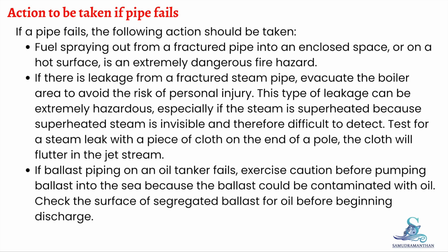In the event of a fractured steam pipe, personnel must evacuate the boiler or machinery space immediately. Steam leakage can cause severe personal injury, especially when the steam is superheated. Superheated steam is invisible and therefore extremely dangerous. A steam leak should be tested using a piece of cloth tied to the end of a pole. The cloth will flutter if steam is present.